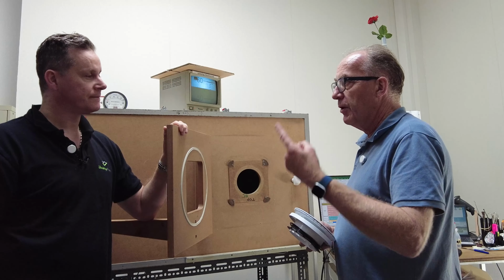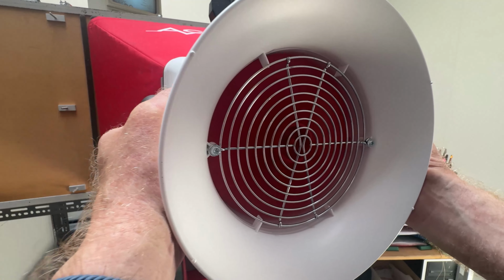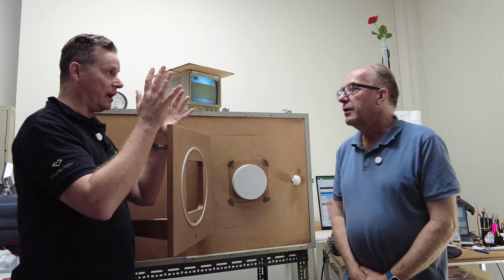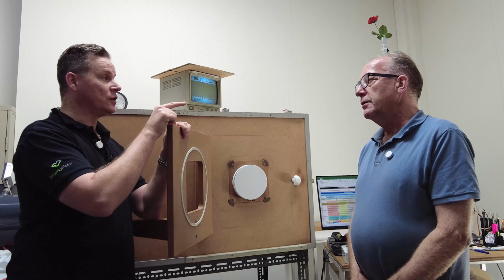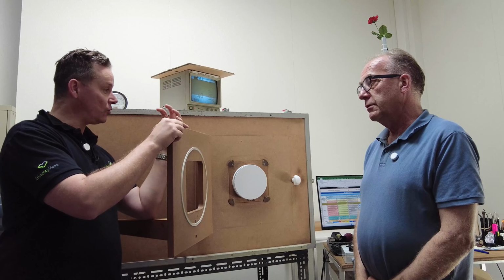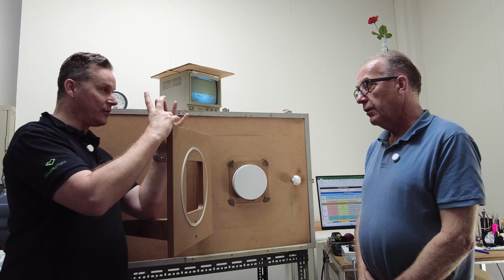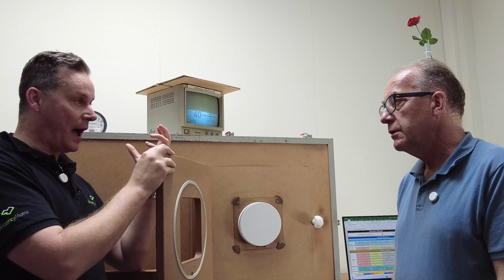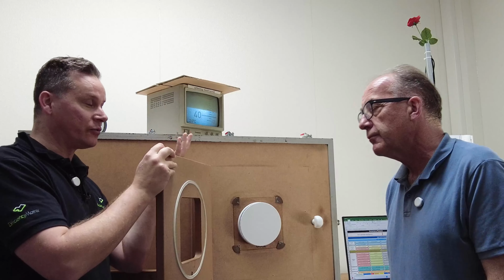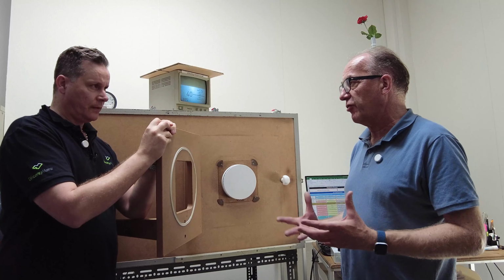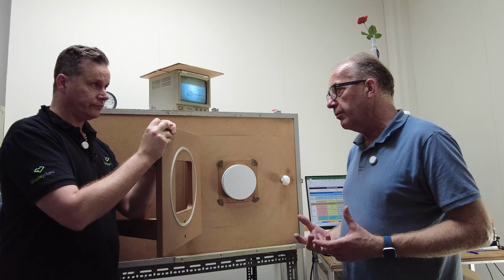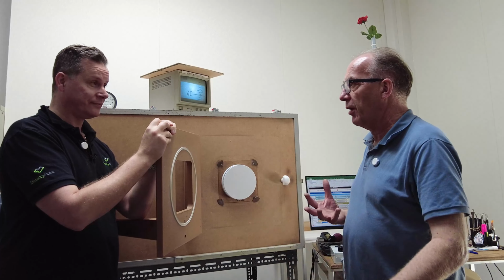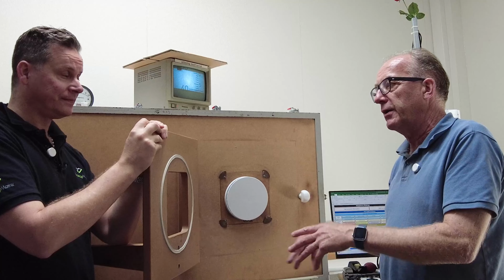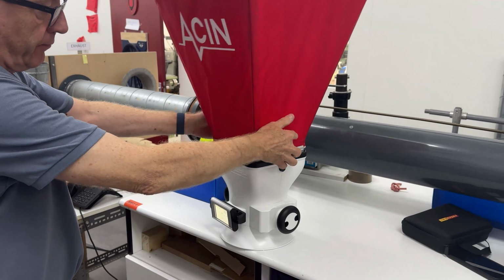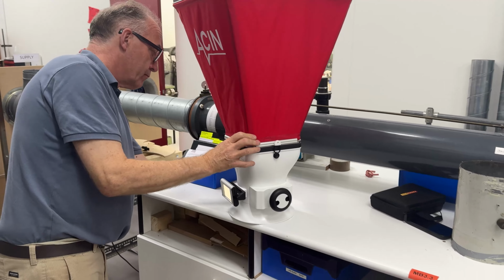So there are two things, flow pattern and resistance, and your Flowfinder solves both issues. It cleans up the air and it pressure neutralizes it. It's even worse when it's in positive pressure because you're trying to smash all this air into a narrow channel, and it's not really how it behaves when it's just open to air as a grill. The flow pattern problem is the biggest with supply flow. The resistance problem is similar for exhaust and supply flow, because if you have to push it through a hole from the back or from the front, it doesn't matter, there is resistance. So Nick, can you demonstrate how the airflows can vary with these different flow hoods?